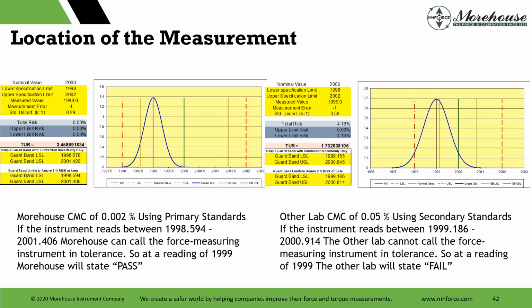Morehouse, here's another good example, 2,000 pound. This time, measured value is 1999. Morehouse CMC of 0.002% using primary standards. The instrument needs to read between 1998.594 right here and 2001.406. You read the instrument in this case. Instrument reads 1999. We can state pass.